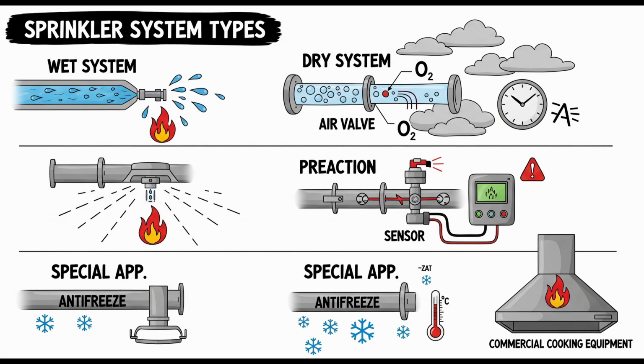What about preventing water from accidentally entering the QOD from the riser side before it's supposed to? That's handled by a listed anti-flooding device. One is required in the connection between the dry pipe riser and the QOD, unless the QOD is listed as not needing one or has built-in anti-flooding features. And its job? Its purpose is to prevent water from entering the QOD improperly during setting, testing, or maybe from minor pressure fluctuations or condensation in the riser. Okay, keeping water out is a constant theme for dry systems and their components. It seems like half the battle.